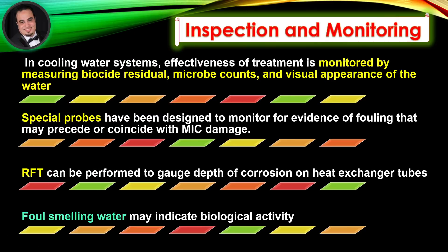Inspection and monitoring. In cooling water systems, effectiveness of treatment is monitored by measuring biocide residual, microbe counts, and visual appearance of the water. Special probes have been designed to monitor for evidence of fouling that may precede or coincide with microbiologically influenced corrosion damage. Remote field testing can be performed to gauge depth of corrosion on heat exchanger tubes.